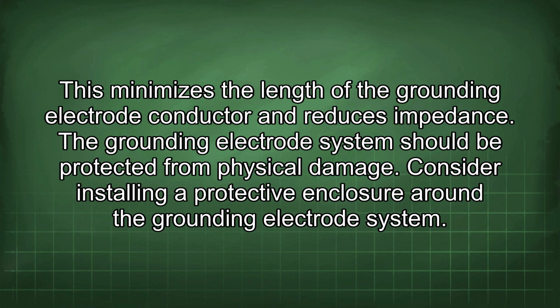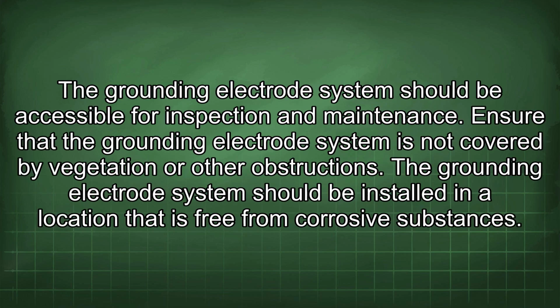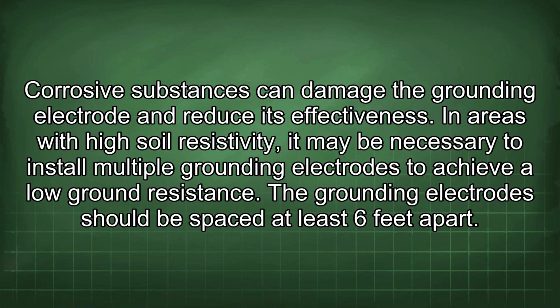The grounding electrode system should be protected from physical damage. Consider installing a protective enclosure around the grounding electrode system. The grounding electrode system should be accessible for inspection and maintenance. Ensure that the grounding electrode system is not covered by vegetation or other obstructions. The grounding electrode system should be installed in a location that is free from corrosive substances. Corrosive substances can damage the grounding electrode and reduce its effectiveness.